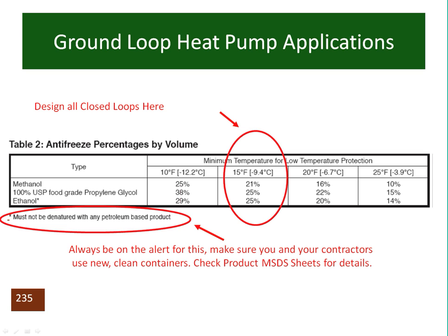Differences between the methanol and ethanol. Methanol has slight toxicity. Ethanol does not. Again, the flammability is a concern. Make sure that you're using the appropriate amount, about 25% fluid by volume with the ethanol to get that 15 degrees, 21% with the methanol. The propylene glycol, again, not my first, second, third, or fourth choice, is a 25% mix as well.